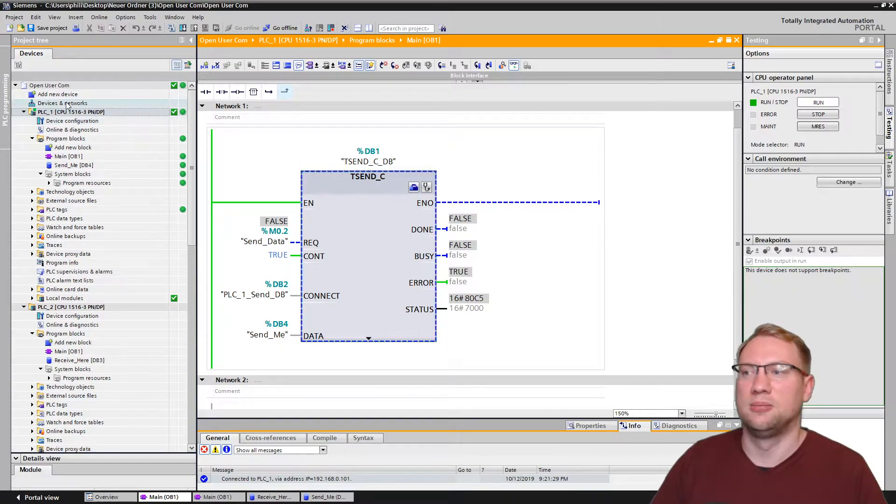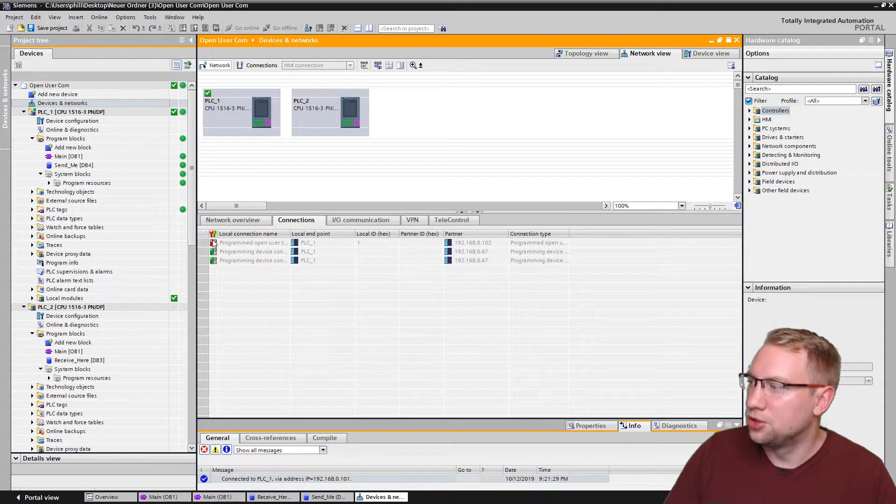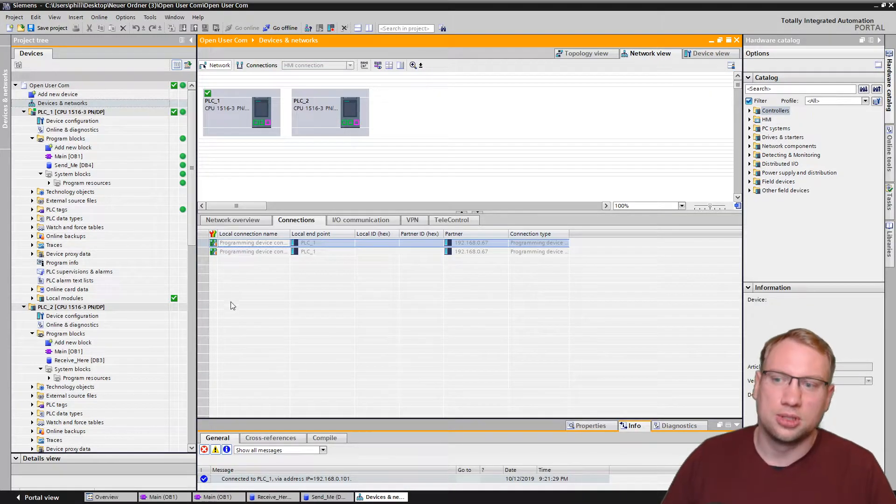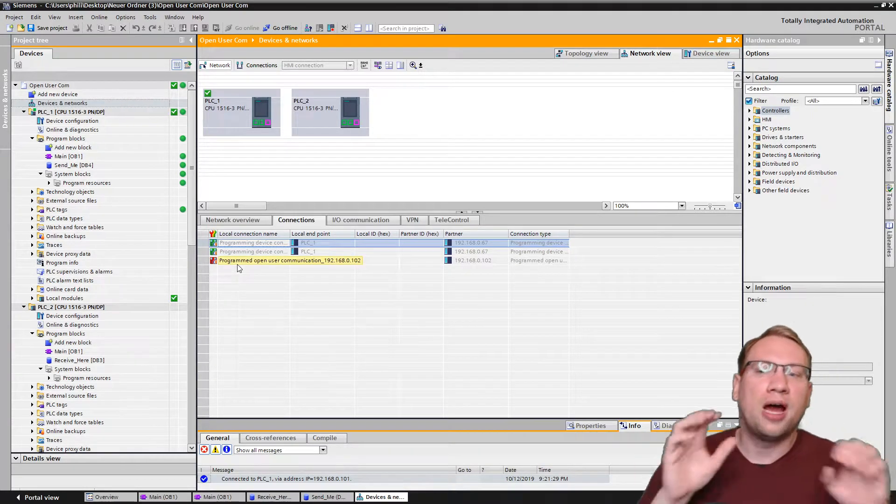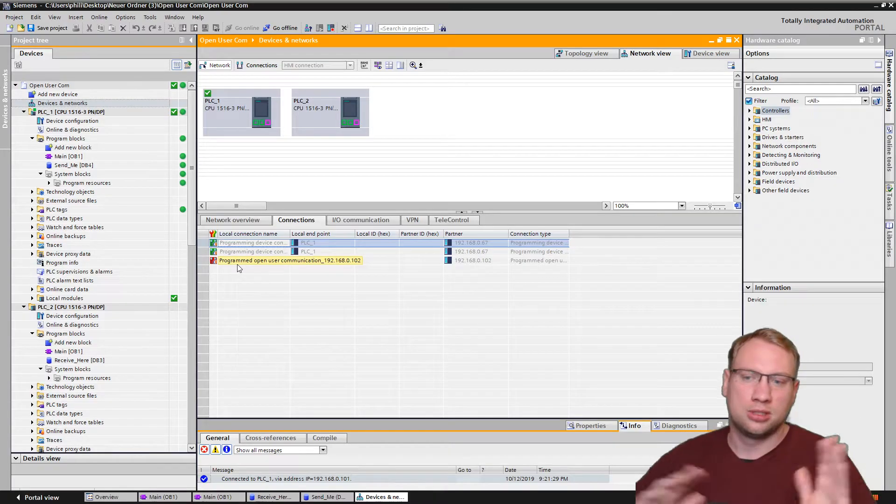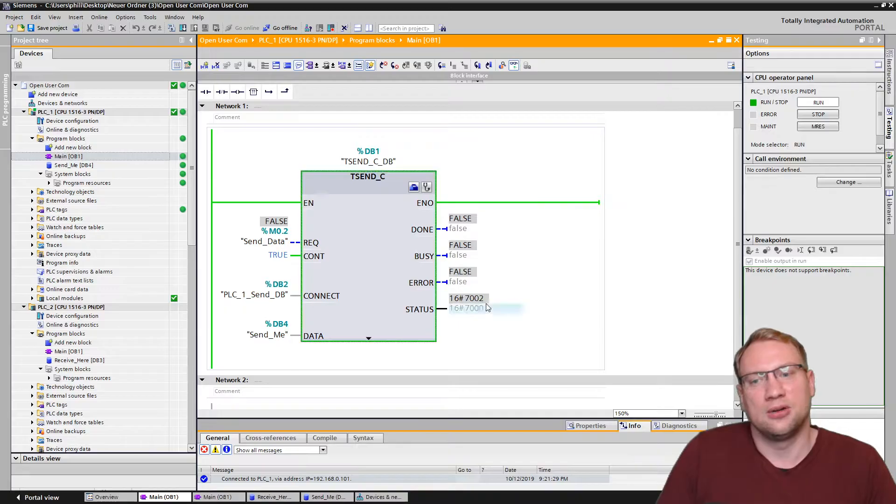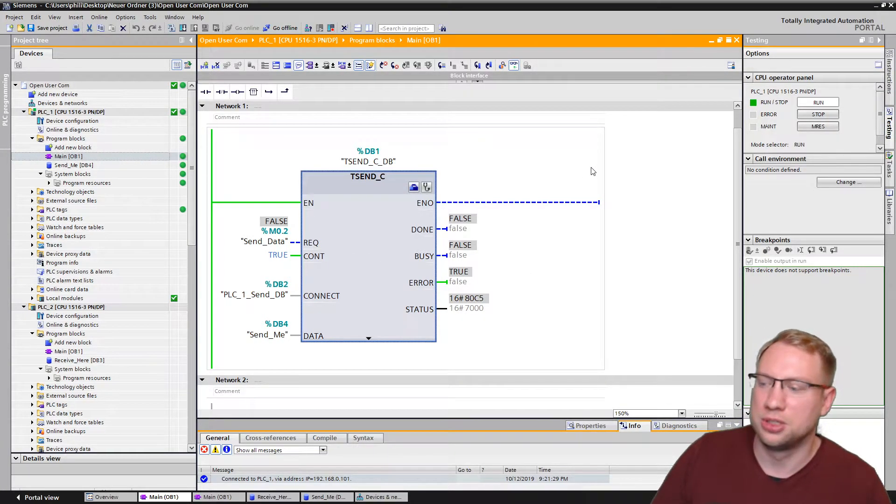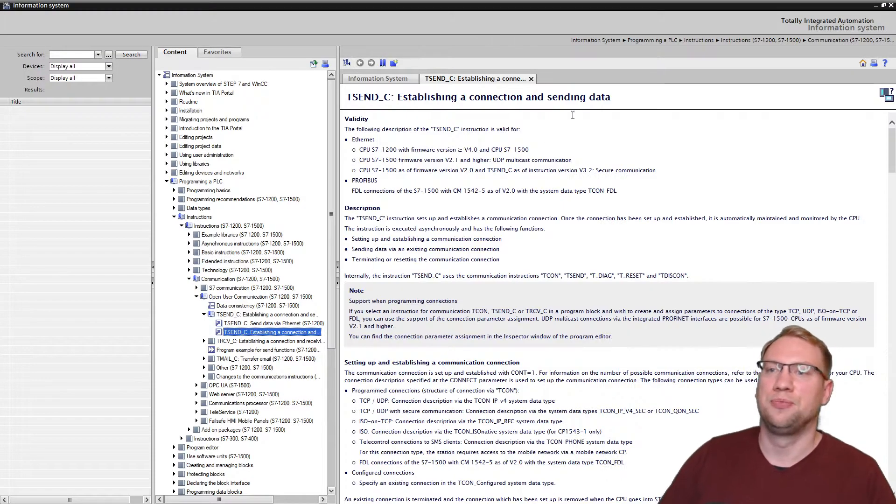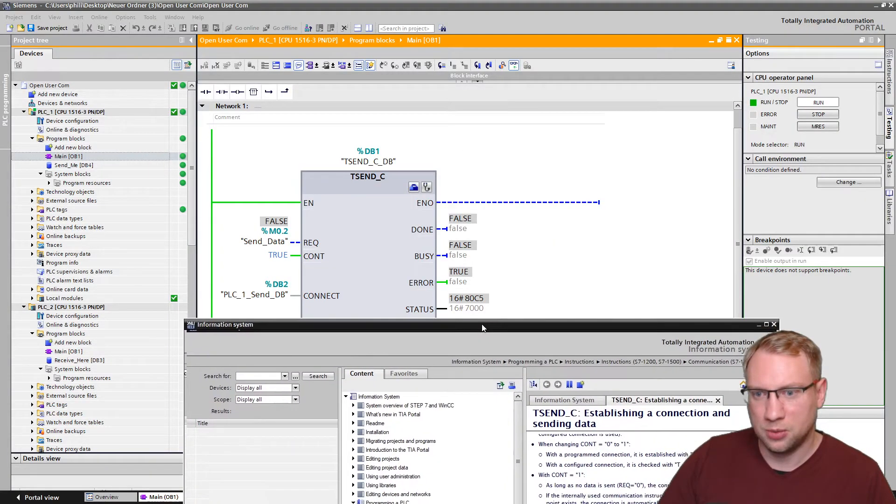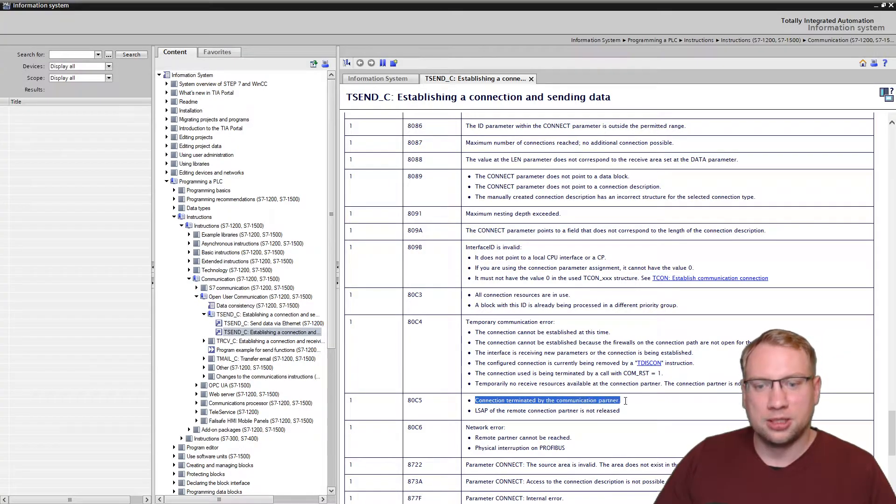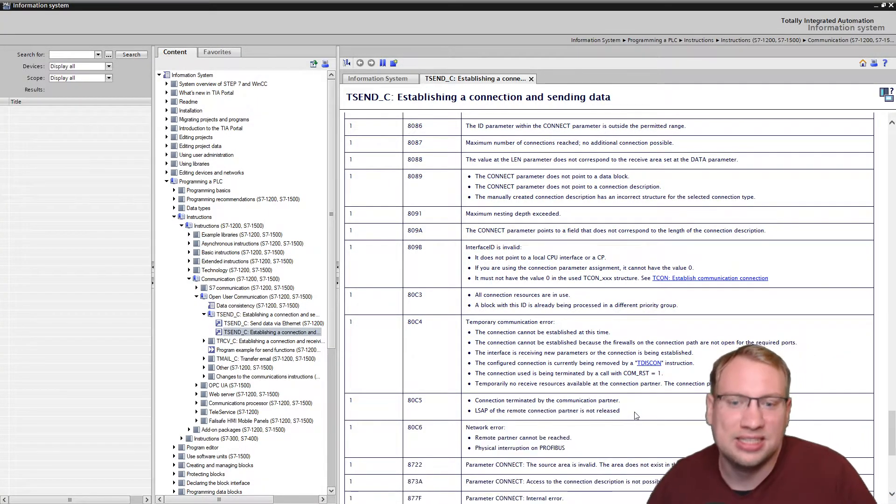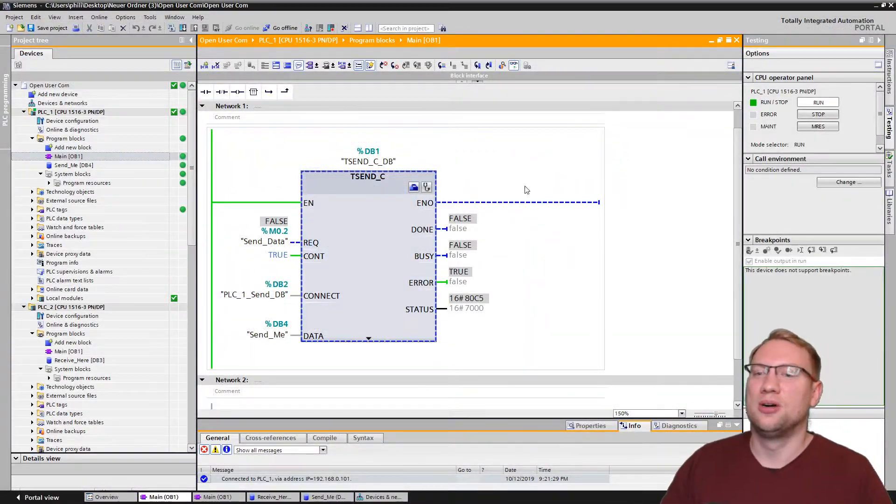If I go to device, if I go here to connections, I should see programmed open user communication is red because sometimes it's there, sometimes it's red, sometimes it's not there. Because TCON is trying to connect sometimes. If it doesn't find something, it will wait, doesn't connect, then it will try to connect again, so it's trying. You can also see here it's doing something, but it always sends out an error. If you need to know the error code, click on it, hit F1, and there's an error code you can look at. I'm hitting F1 here as well, opening my information system. If you scroll down, there's the error code list. The one 80C5. 80C5, connection terminated by communication partner, remote connection partner is not released. We don't get an okay from the partner. Make a guess, the partner needs also a block.